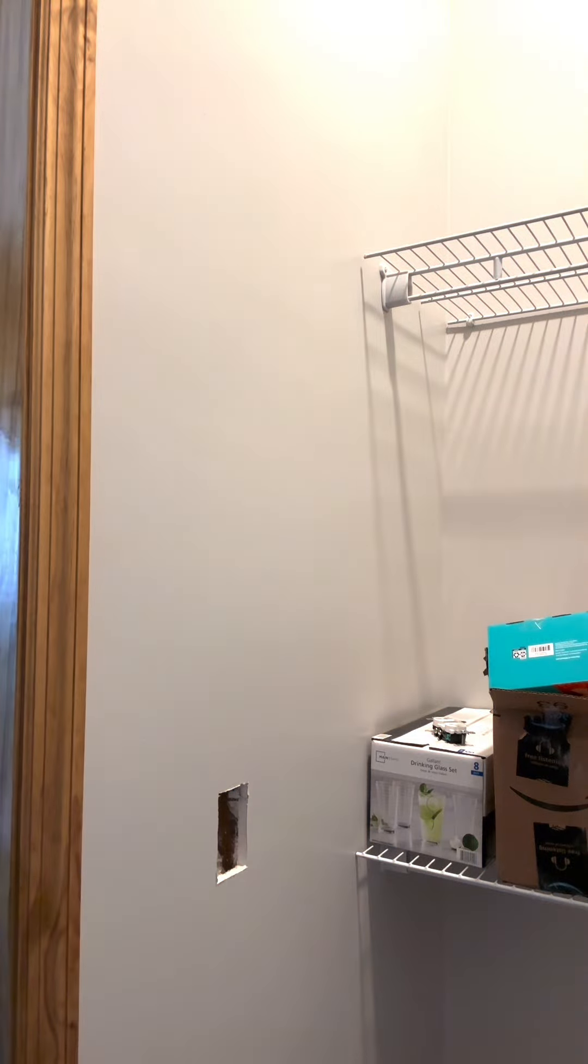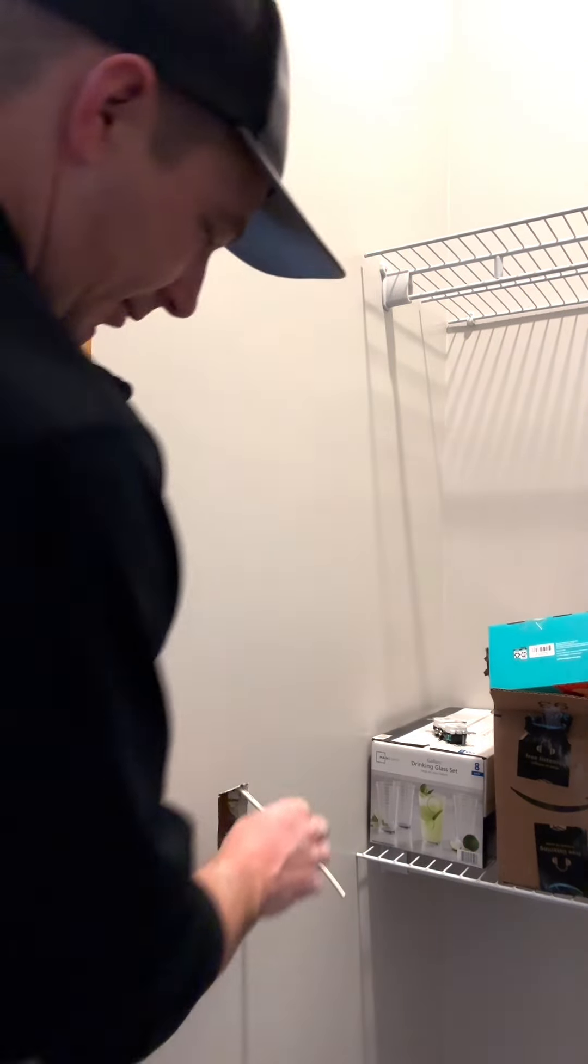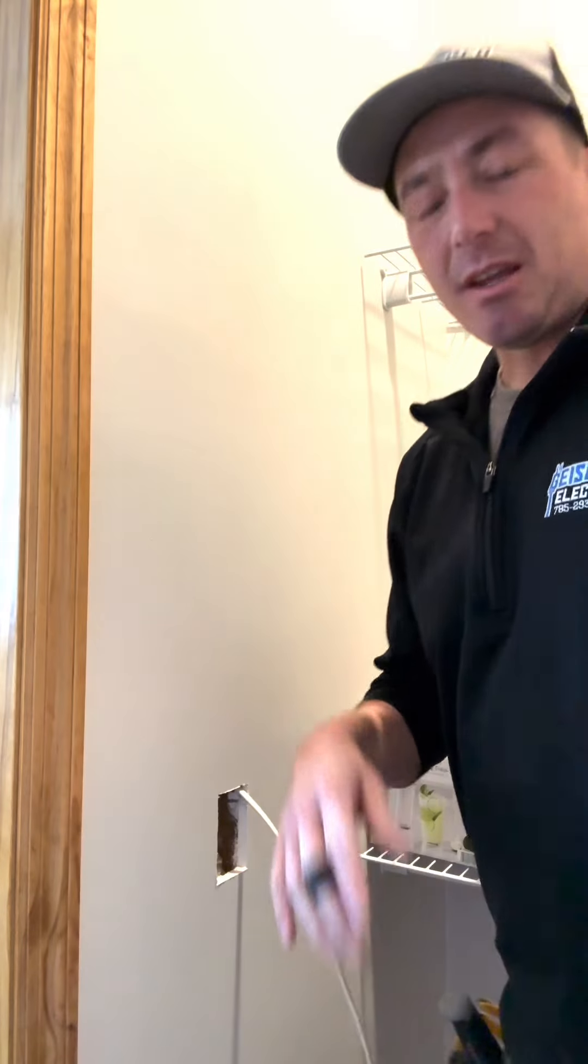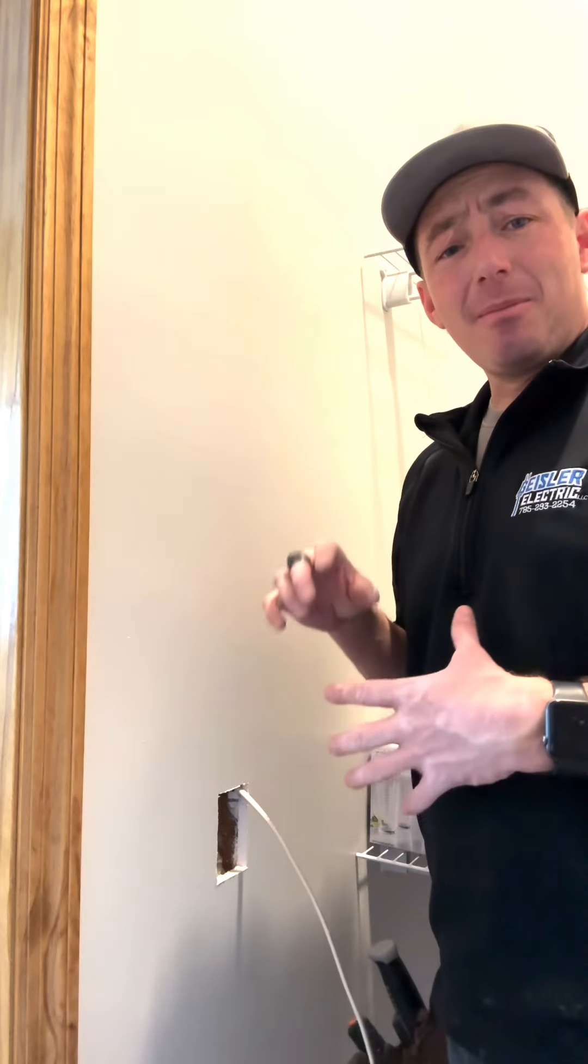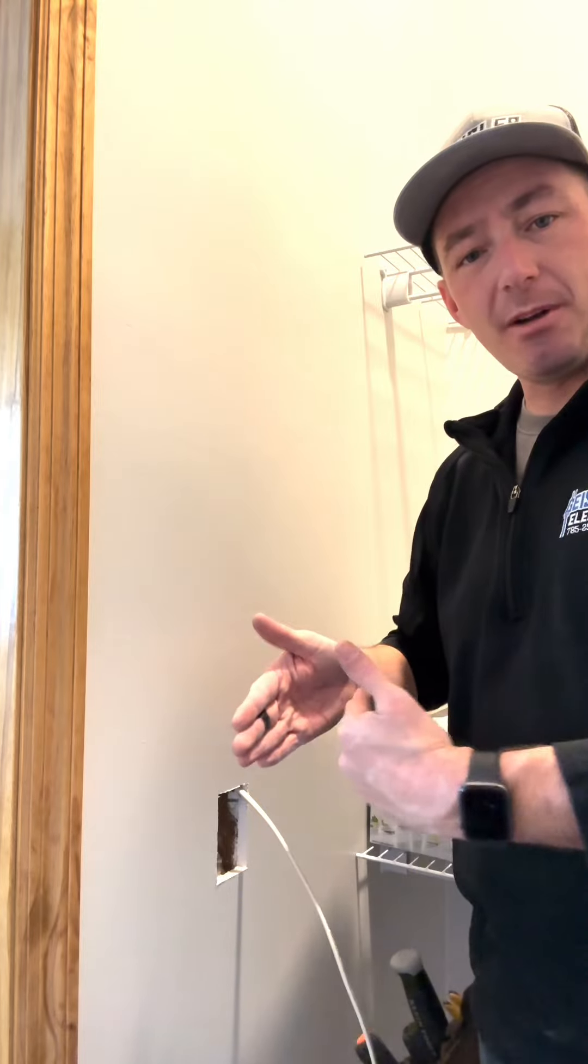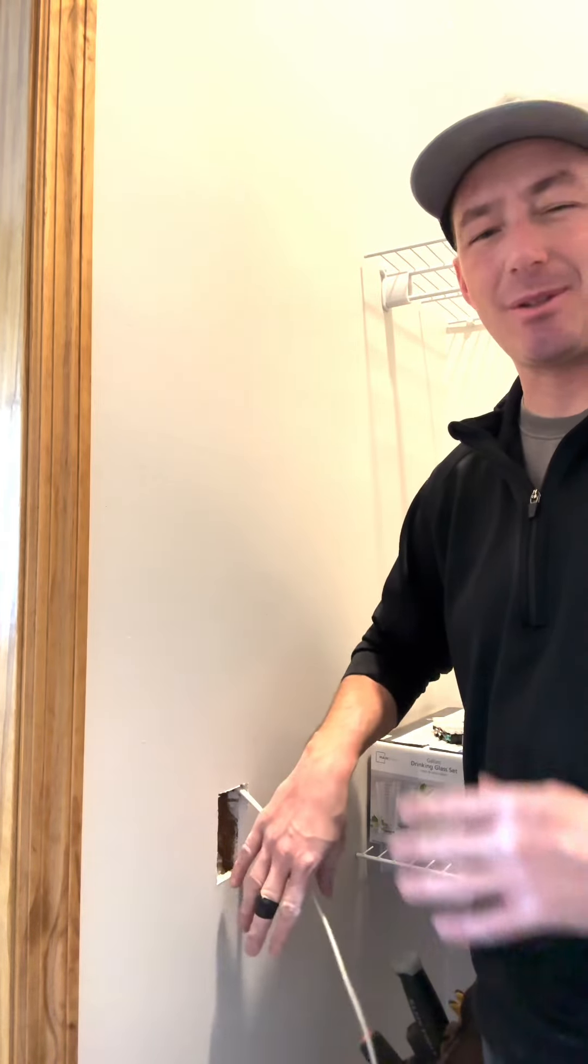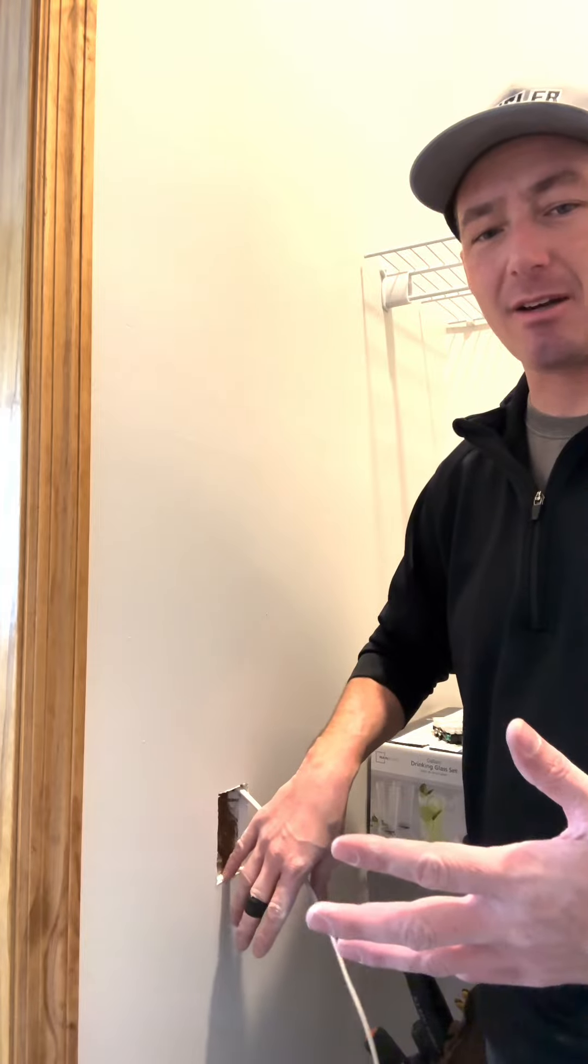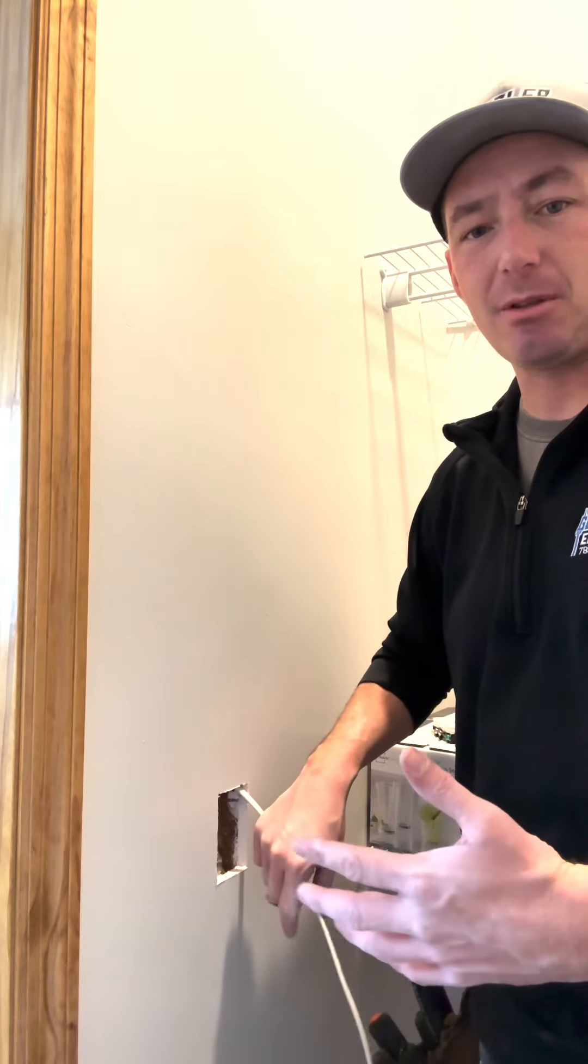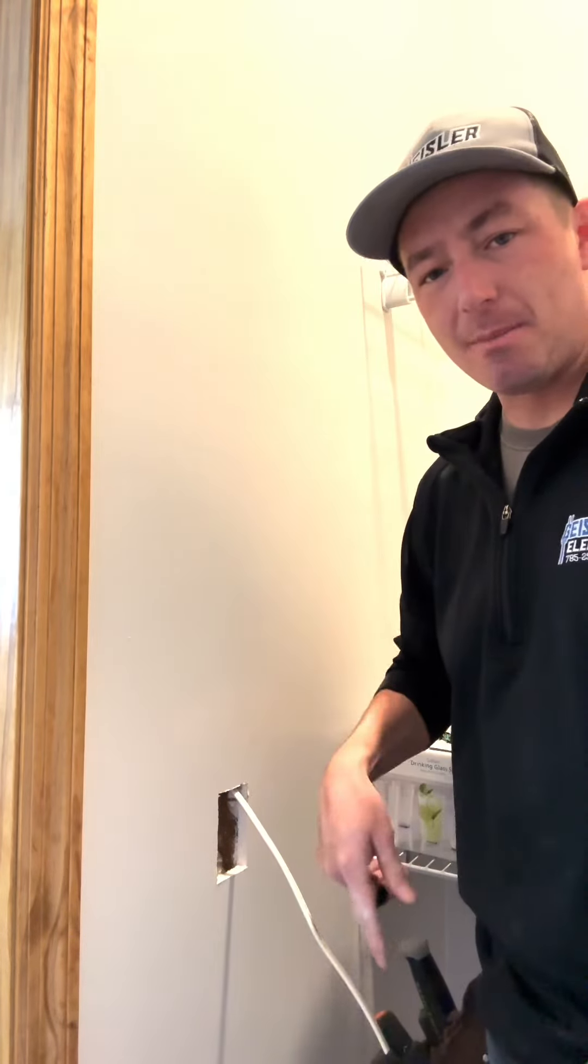I'm just going to use 14-2 because that's what's feeding it. I'm just going to push this down. That's right in line. Now the reason that I went out the bottom of that box is because this wall is only a 2x4 thick. There's not enough room for both of those boxes. This height on this receptacle doesn't really matter. He just wanted a receptacle in here.